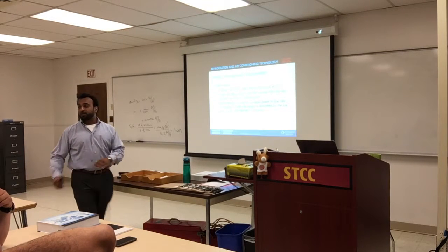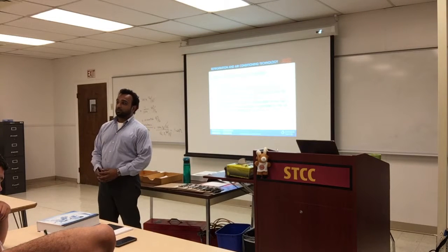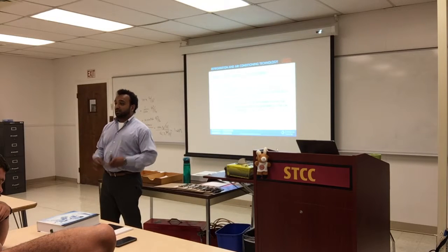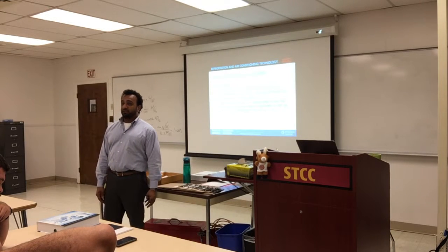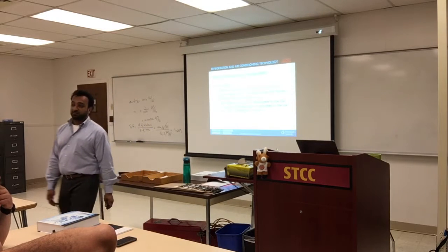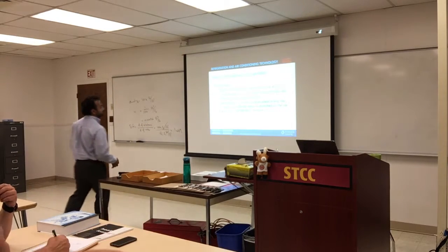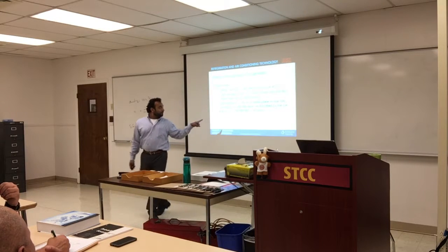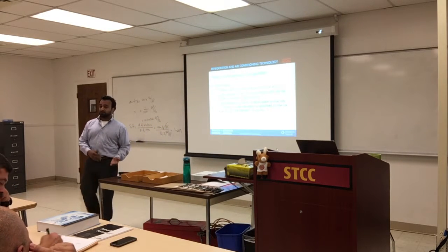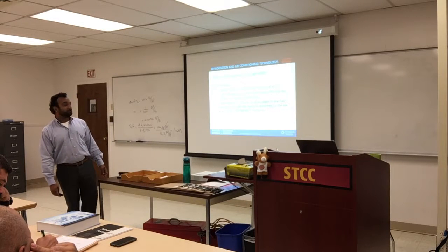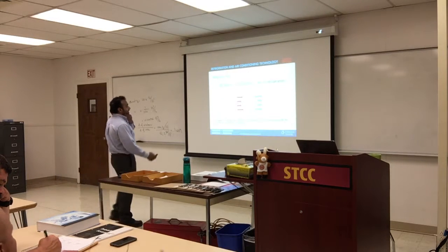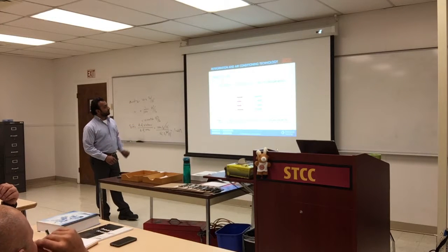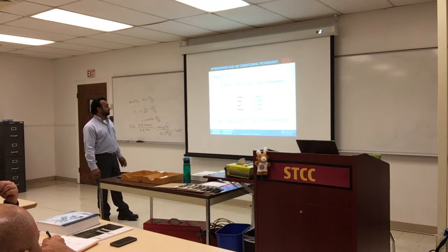So if you buy a big block of ice, that's 1 ton, which is 2,000 pounds, and leave it for 1 day, if it melts in 1 day, then you have 12,000 BTUs. I don't think you need to remember all that, but for conversion's sake, just remember this number, 12,000 BTUs. That's the conversion between BTU and tons of refrigeration. Here's the block of ice, and this is how much it takes to melt the ice completely.